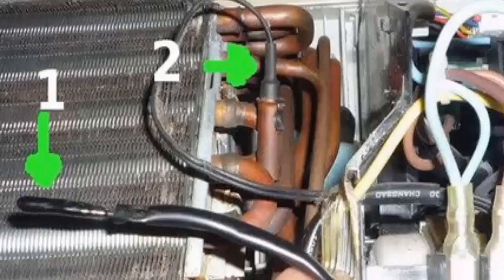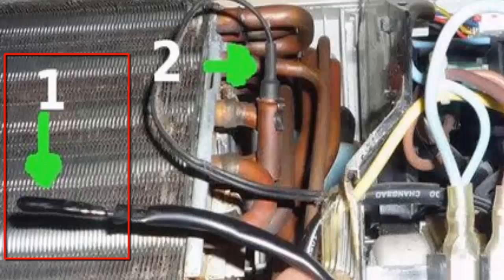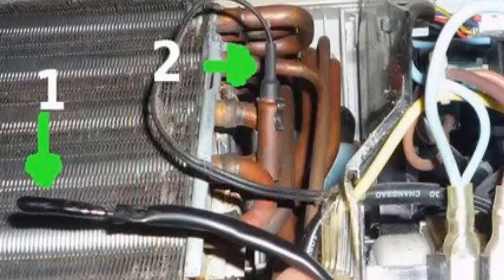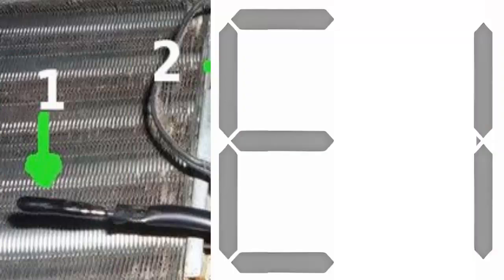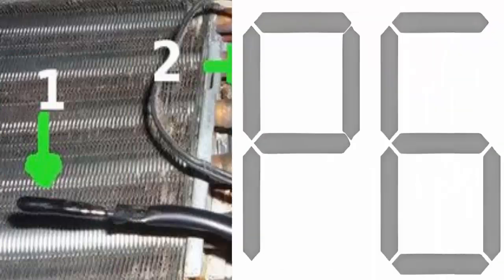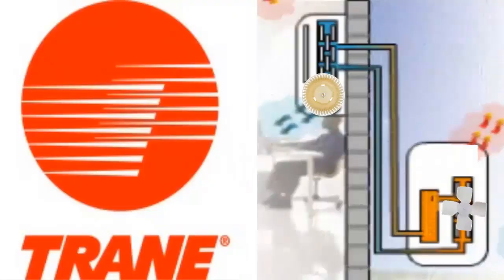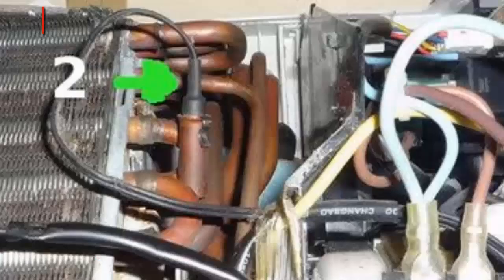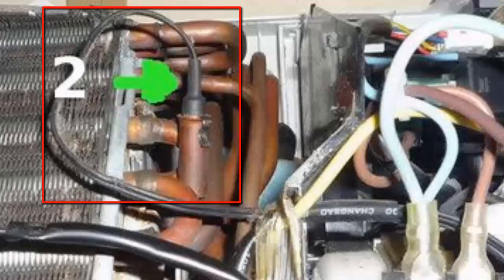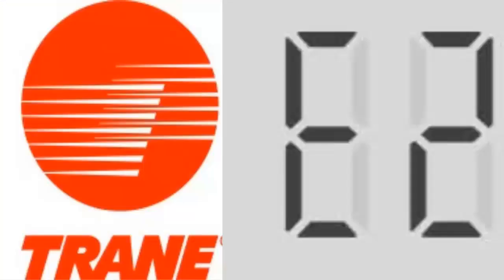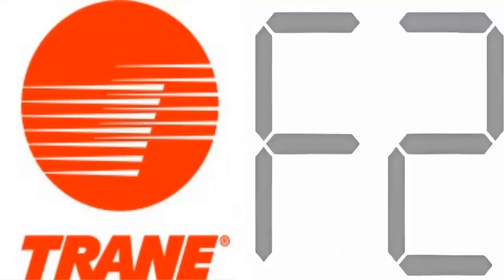1. When there are issues with the temperature sensor located in the indoor unit, which measures the temperature of the room air drawn in by the indoor unit fan, codes E1, F1, and P6 can be generated. 2. When there are issues with the temperature sensor located in the indoor unit, which measures the temperature of the evaporator, codes E2, F2, and P5 can be generated.